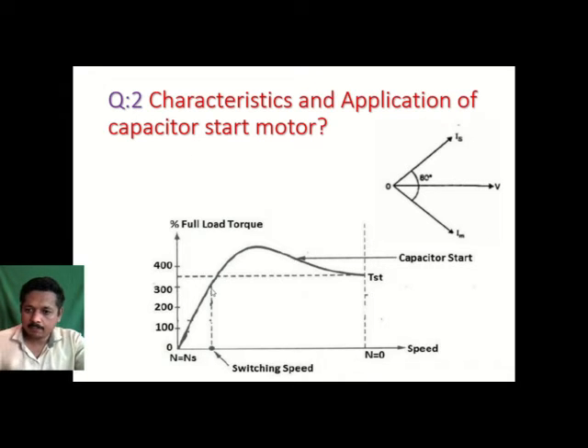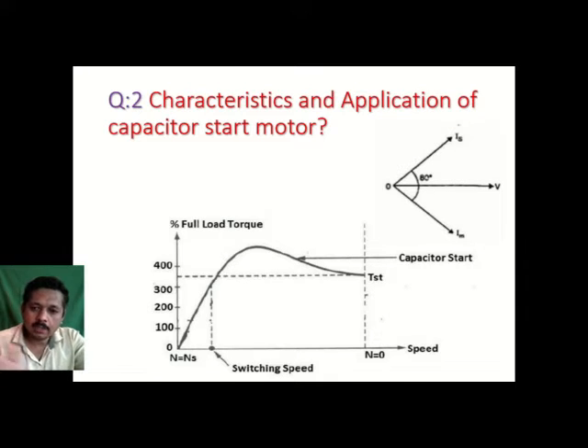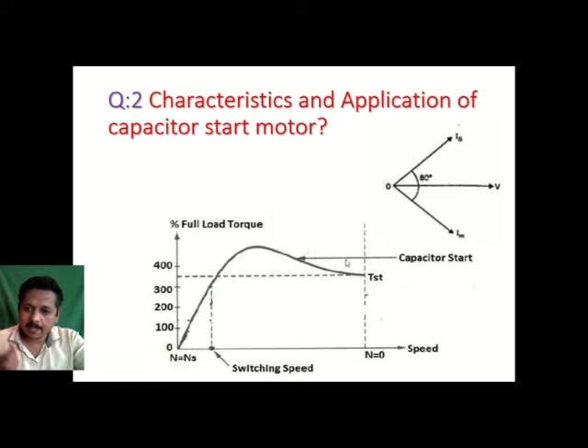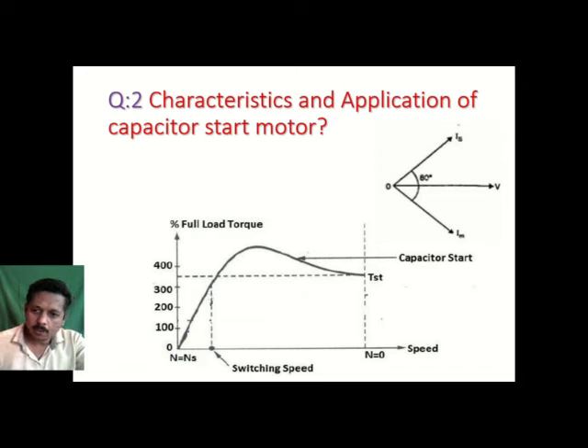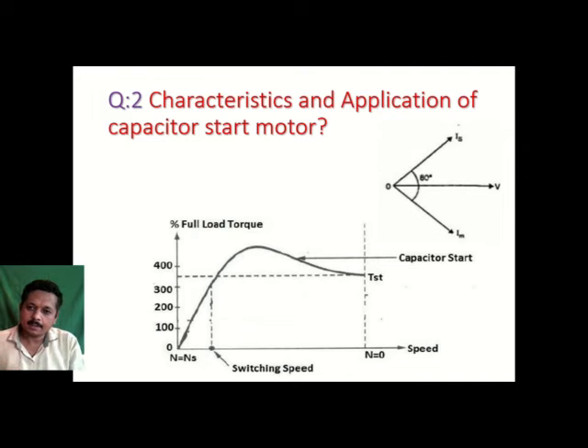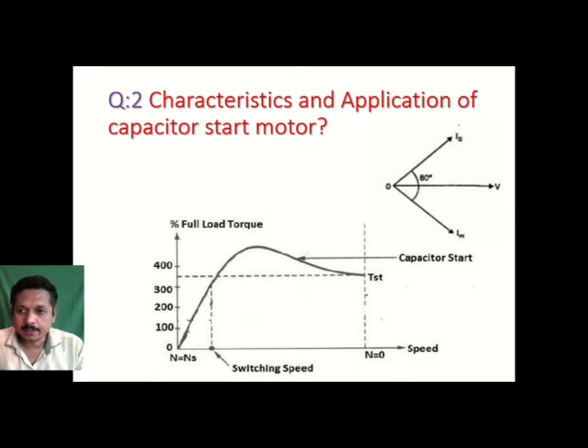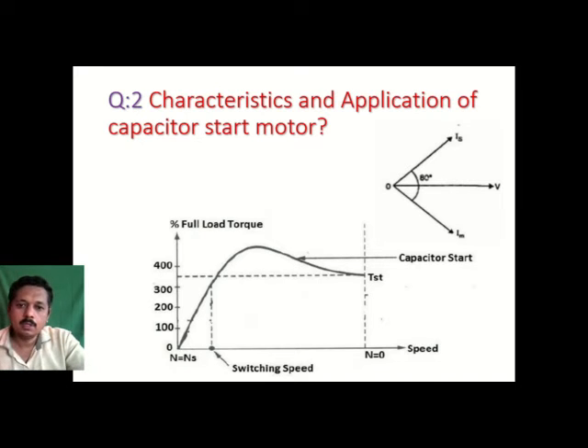Once the motor starts, at 75 to 80% of synchronous speed the centrifugal switch operates and disconnects the auxiliary winding, so the motor runs only on the main winding. This is the similarity between the resistance and capacitor start motor — their main winding is made of very fine copper material. So the running characteristic is similar to the resistance split phase motor, but we get a much better starting torque. In running, both resistance and capacitor start motors are similar.